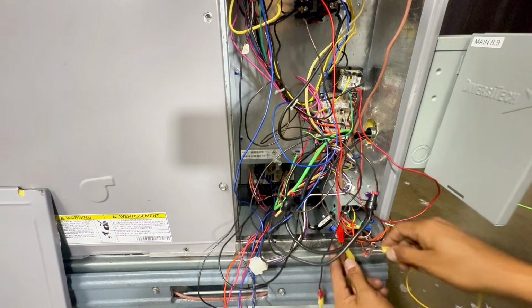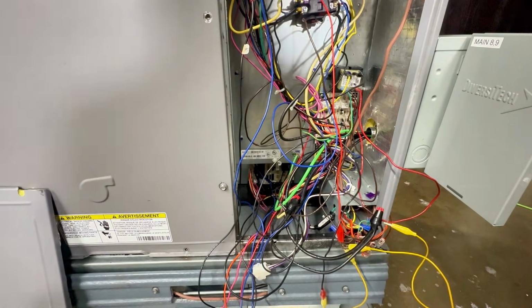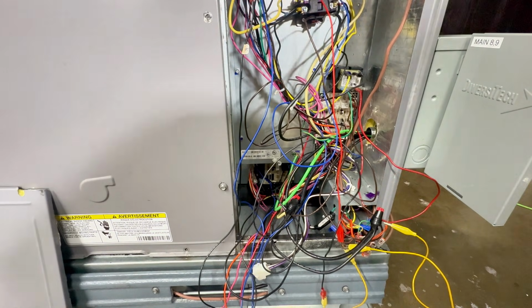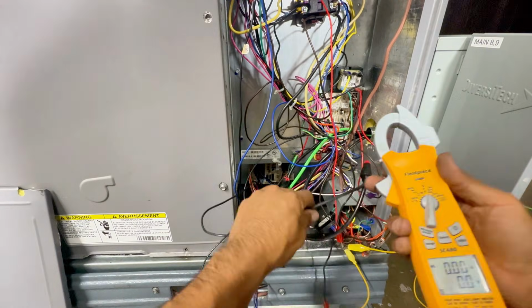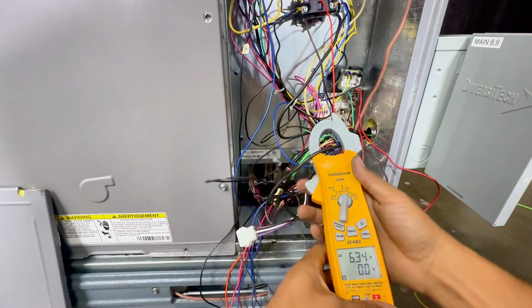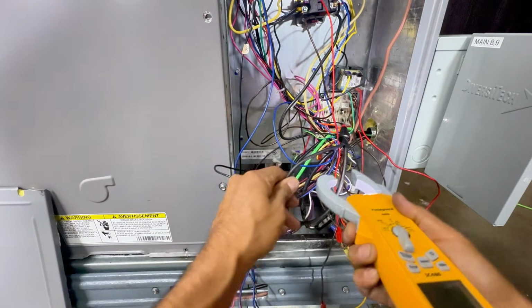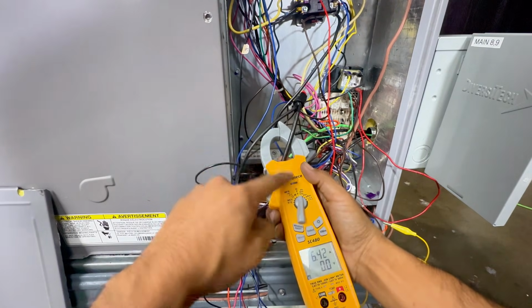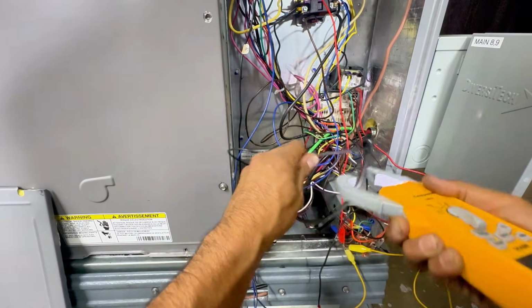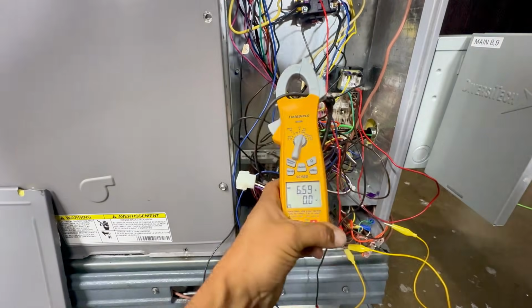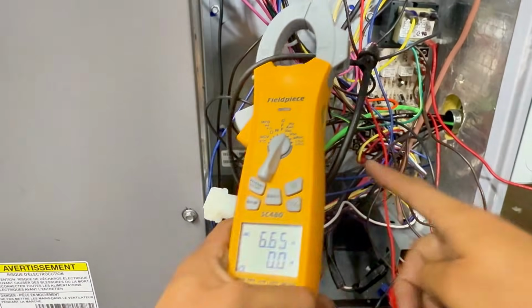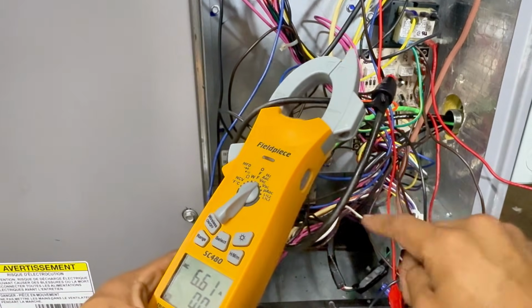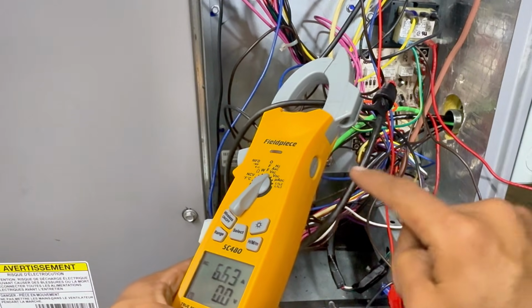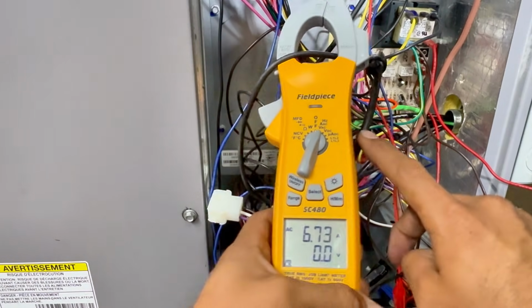Okay, give it a second. All right. Now I'm gonna check the amp draw, right? Amp draw. Okay, and it doesn't matter if it's on this side of the cable or on this side. And of course, if you're working on older systems, be careful it doesn't have a nick. If you have copper exposed and you touch that, you're gonna get hurt. So be careful with that.